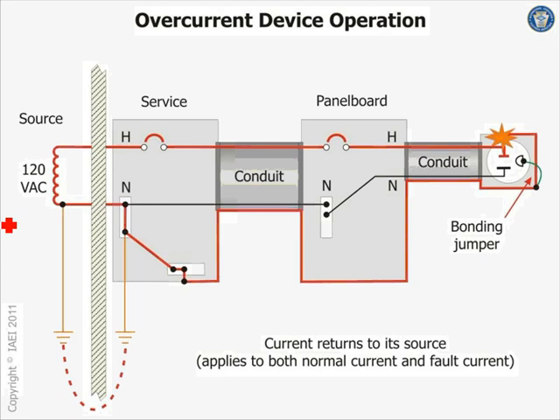For your ground fault, if you lose a neutral, what happens if you lose your neutral right here, guys? Go cut the neutral now. Do you think your power system will work? Anybody want to try it? Go get rid of the neutral. There is no other phase, which is safer here. That's how they use it in Europe and all over the world. They use 220 here instead of 120. Everything is one hot and a neutral coming to the house. So 220, if you lost the neutral, what happens?